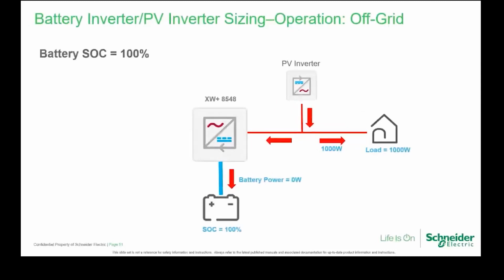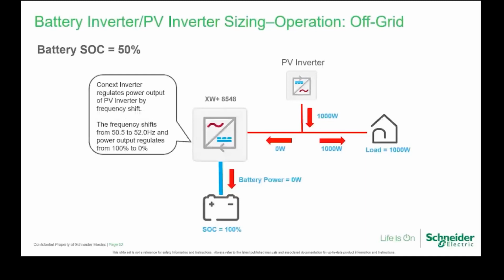But now if the battery is at 100%, you've still got 1,000 watts going to the loads, but because there's nothing else, that 4,000 will try to go into the XW Plus. Unfortunately, it can't go anywhere because your battery is already fully charged. So what happens is the Conext inverter regulates the power output of the PV inverter by frequency shifting. This frequency shifts from, say, 50.5 to 52. That's a European model. Power output is regulated from 100% to 0%. So the PV inverter will derate itself to 1,000 watts so that 1,000 watts can go to the loads and nothing can go back into the XW Plus.